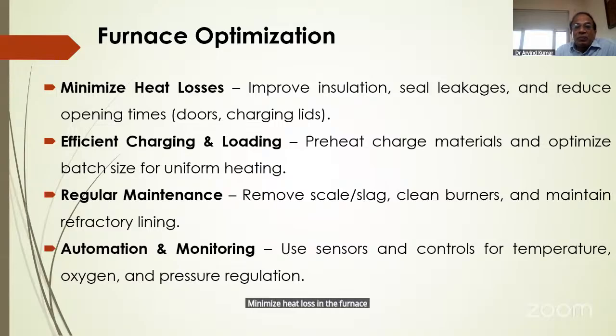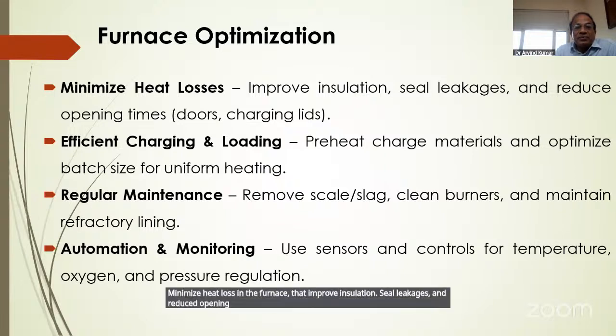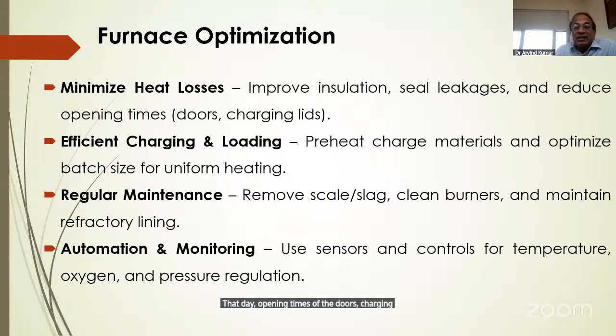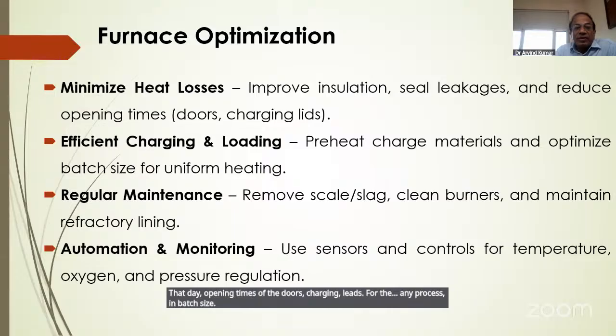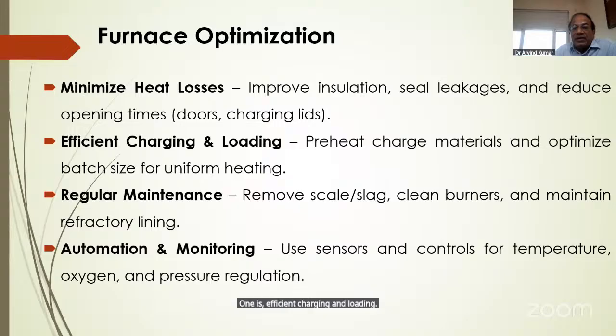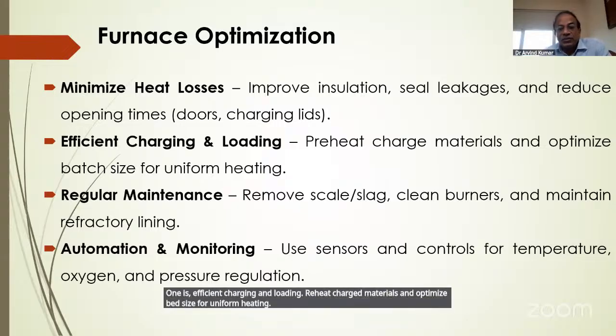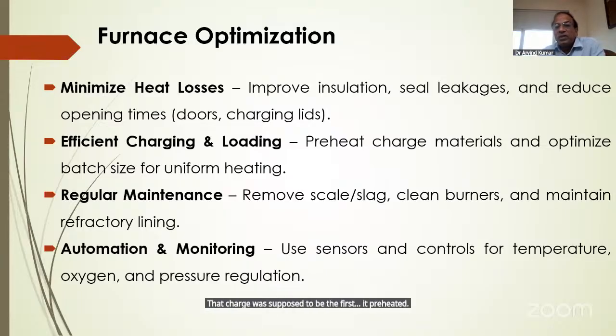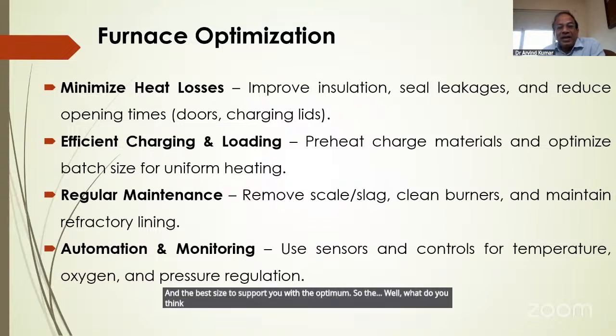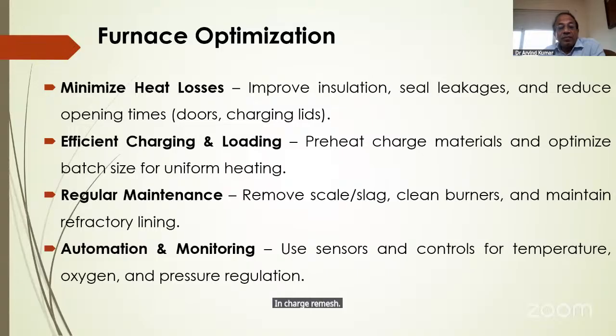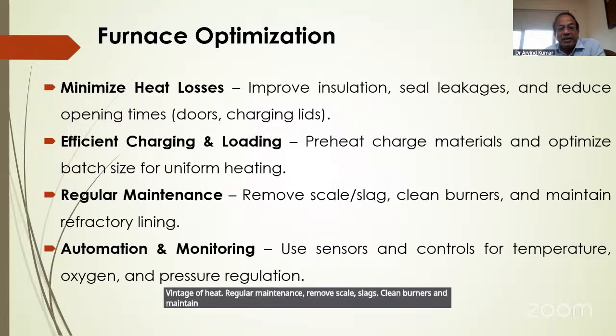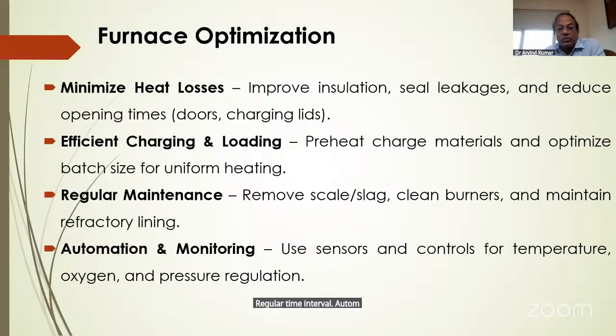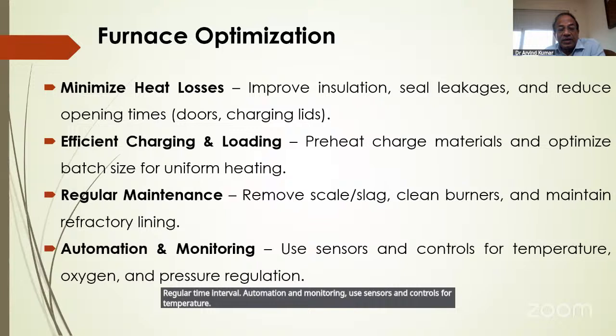Minimize heat loss in the furnace: improve insulation, seal leakages, and reduce opening times, that is, opening times of the doors and charging lids for any process in batch-type furnaces. Efficient charging and loading: preheat charge materials and optimize batch size for uniform heating. The charge should be preheated first, before it is put into the furnace, and the batch size should be optimum, otherwise overheating or underheating of the charge remains, and that leads to wastage of heat. Regular maintenance: remove scale and slag, clean burners, and maintain the refractory lining at regular time intervals. Automation and monitoring: use sensors and controls for temperature, oxygen, and pressure regulation.